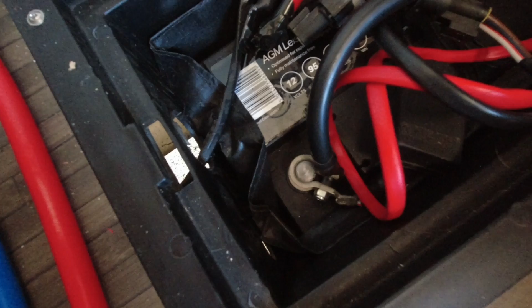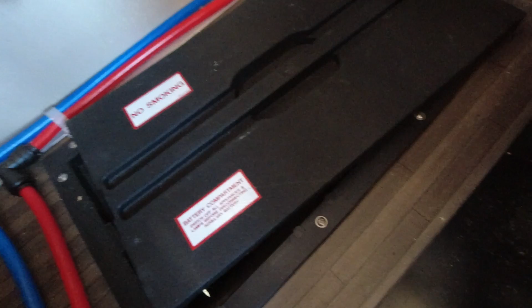So you can see there that I've attached the new cables directly to the battery terminals, and what I'll probably have to do is drill a couple of holes in this lid for the cables to come out. I shall put the circuit breaker probably on this wall here, and then the inverter itself will go on here, so that'll be tucked out of the way inside the storage compartment.